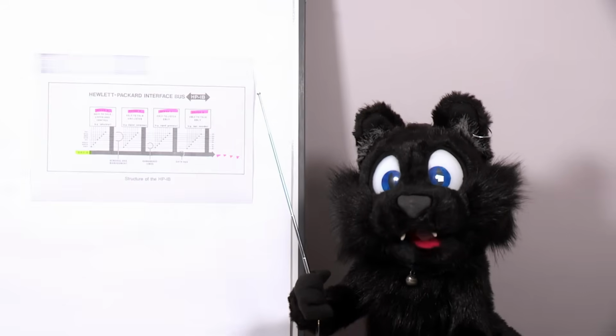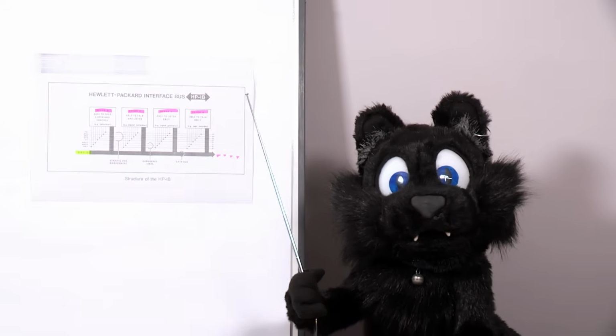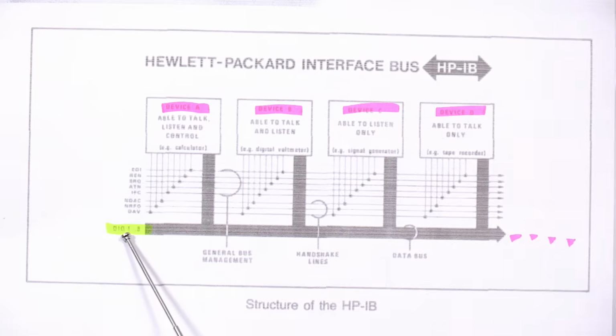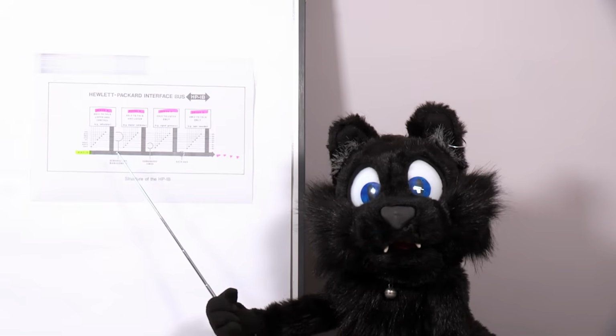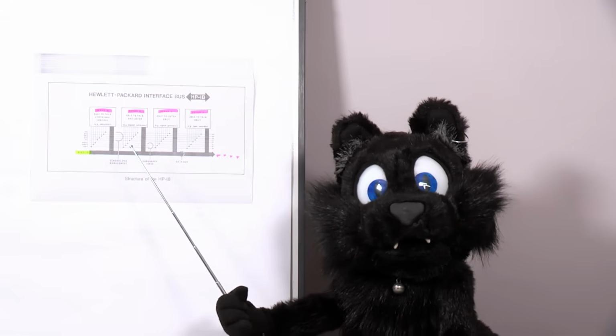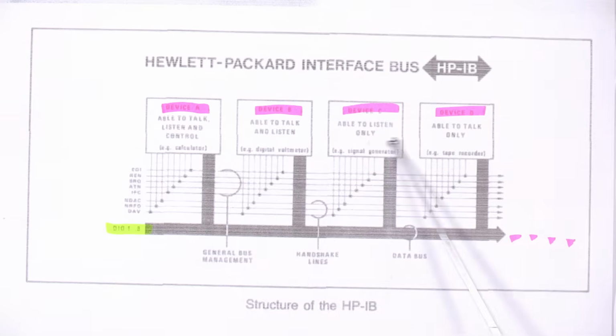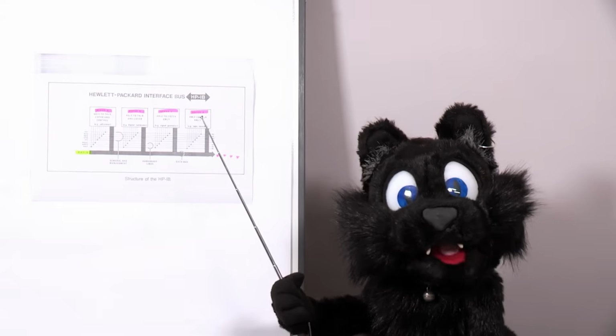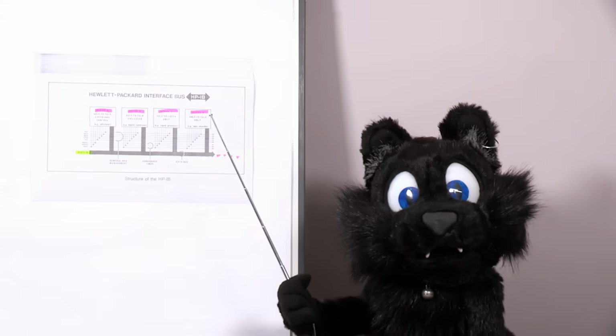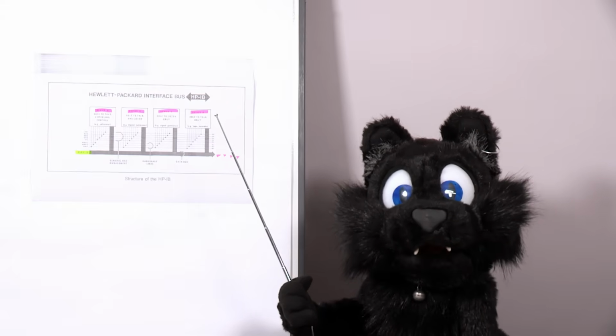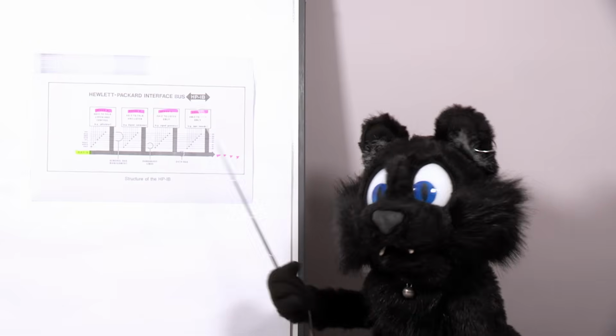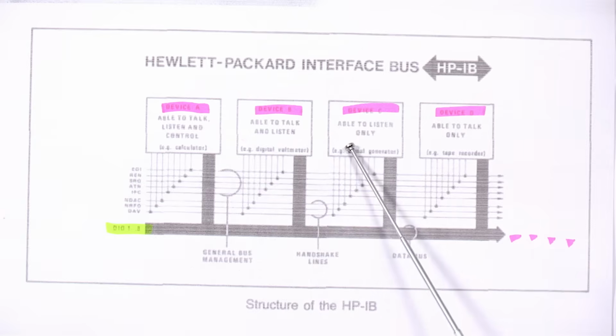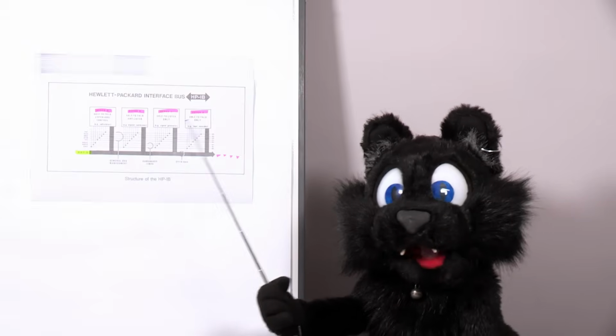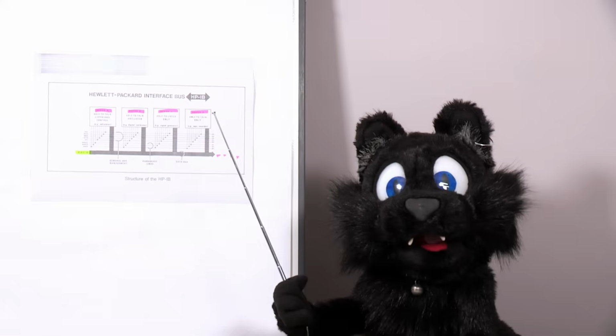Now here's a good point to explain a few basics about GPIB. The bus has 8 data bits, usually labeled D1 to D8, but I've seen D0 to D7 too. It would be too easy otherwise. The bus can have up to 15 devices connected, but supports up to 31 addresses. This is because it uses 5 bits for addressing, and all ones are a special case. At any given time, only one of these devices is in control of the bus. The device that controls the bus is the one that can drive the data bit lines.